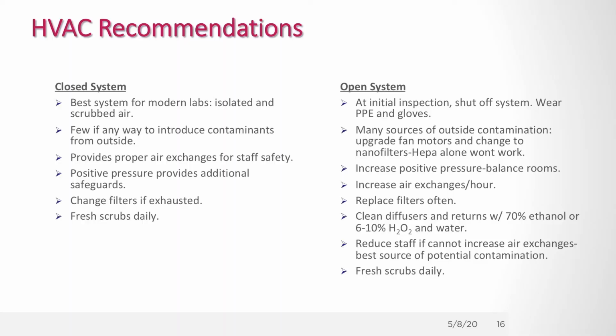So how do our labs compare as far as HVAC goes? On the left is the closed system, on the right the open system. These closed labs are best because they literally scrub the air, reduce outside contamination, provide the proper air exchanges laboratory staff need, and maintain positive pressure, which decreases the amount of contaminants that can come in from outside.